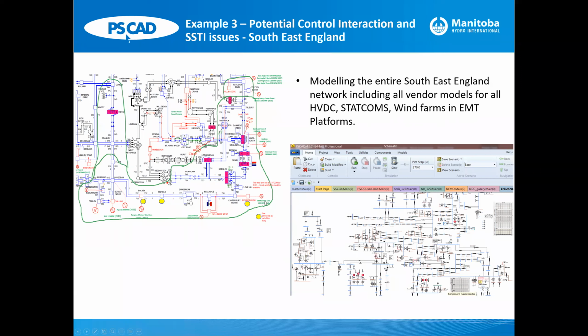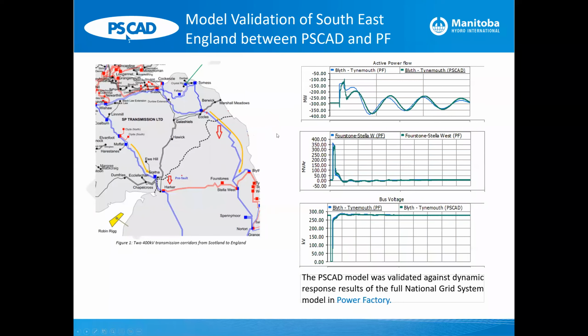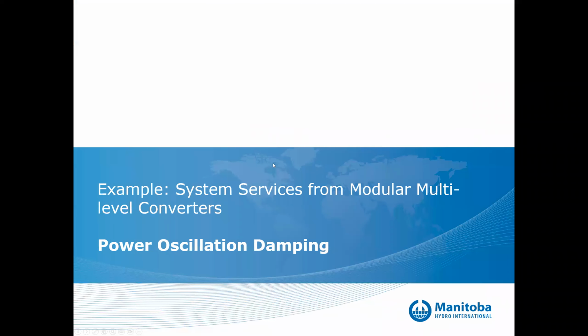We found that, in order to get a good representation of the system, we initially wanted to model only a part of the system and include all the power electronics. But then we found that to get an accurate measurement of the system, we need to go further away. So how do we know whether we should go for a small system representation or a very large one? It depends on the study you're trying to perform. But generally speaking, for most typical studies with control interaction and these types of phenomena, it's necessary to use large-scale models. Model validation is an extremely important part of the study. When you get your data from PowerFactory, PSSE, or any other format, it's very important to initially validate it between PSCAD and PowerFactory. I will discuss this a bit further going forward.